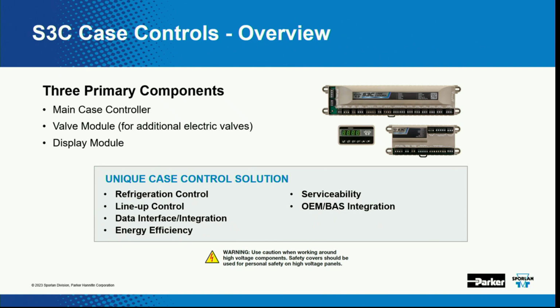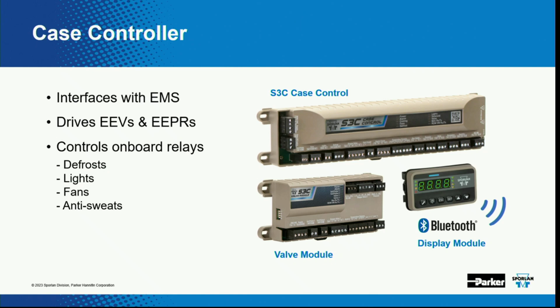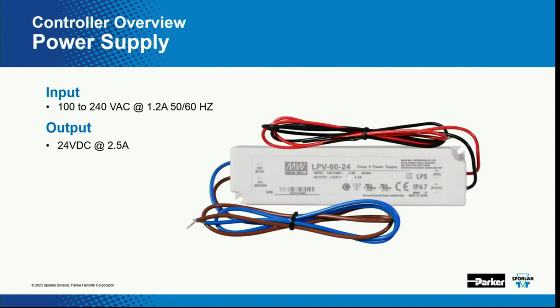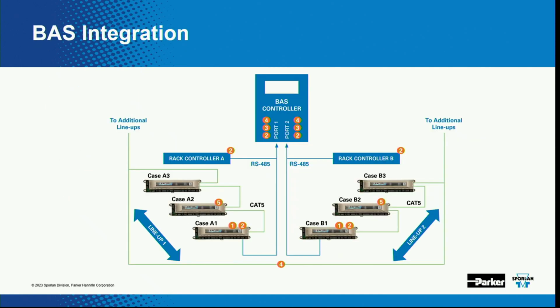I guess what I would share is that there's a number of inputs and a number of outputs on this board. So the inputs are going to be temperature inputs, pressure inputs, switches for like the door switch, or motion detection, or occupancy detection. So is this going to be the same system for the CO2 racks? Yes. CO2 cases, yes. Exactly. You can use the same board, same setup. We can also control the defrost with these, and control the lights. So the lights are on a timer to make sure that they are on and off at the right times. Fans, anti-sweats. So that's all being controlled with this if the customer wants them to be. They all need a power supply. And as I said, they all come back to the BAS controller.